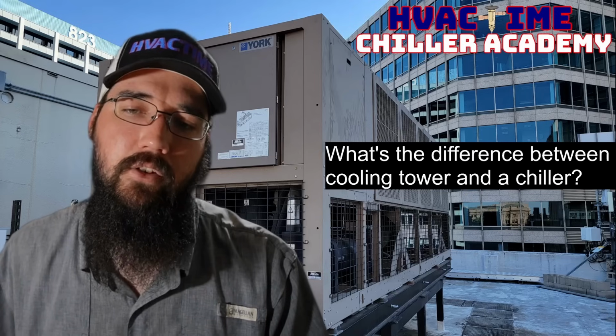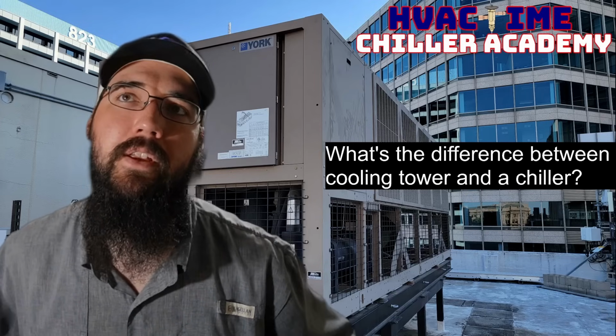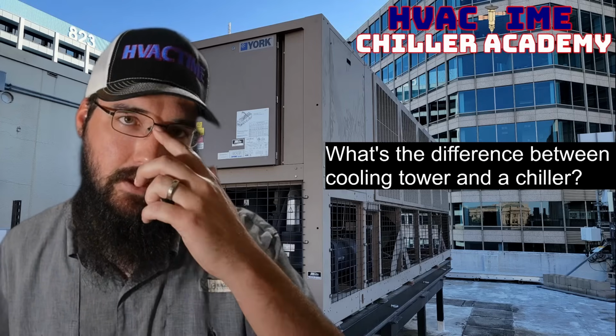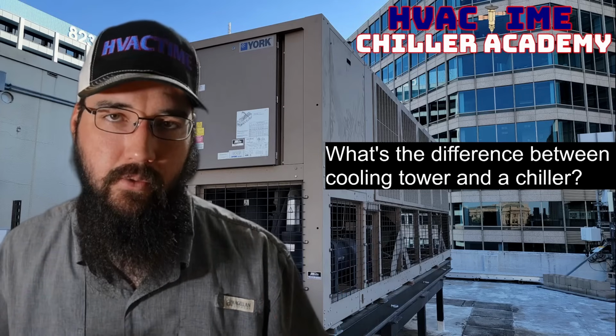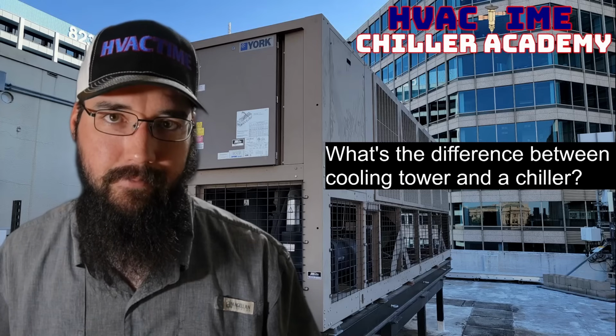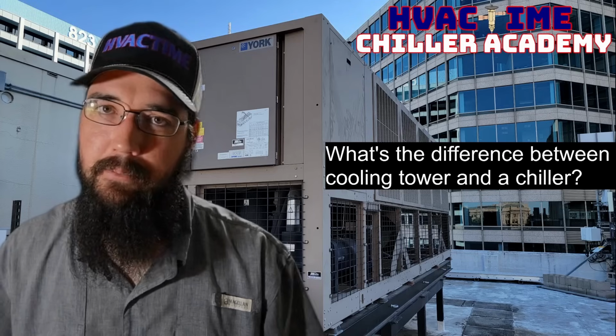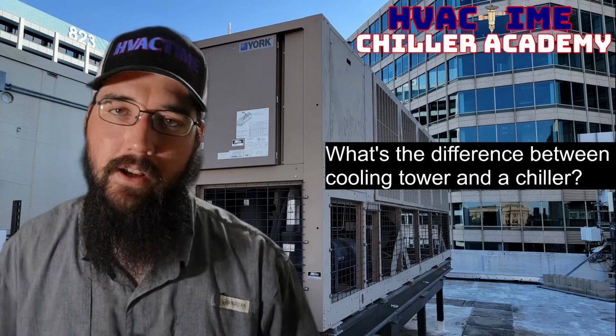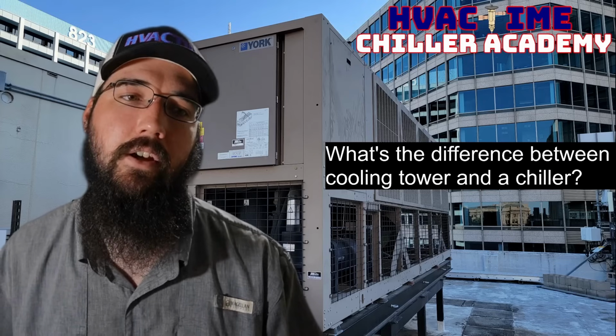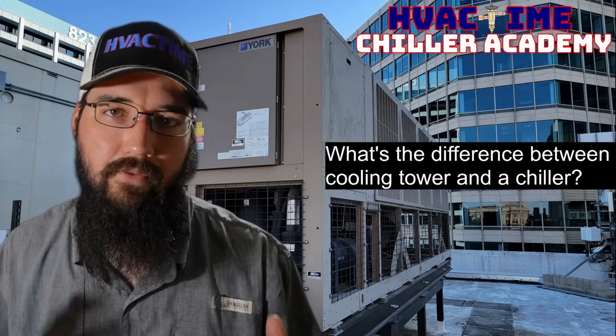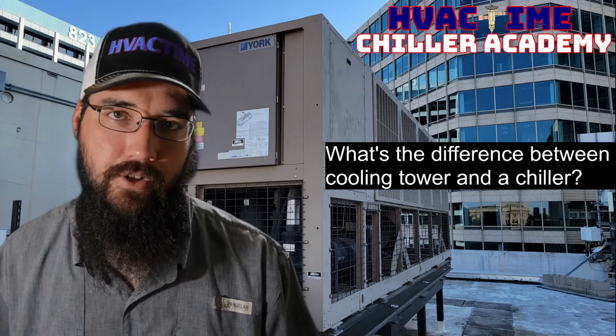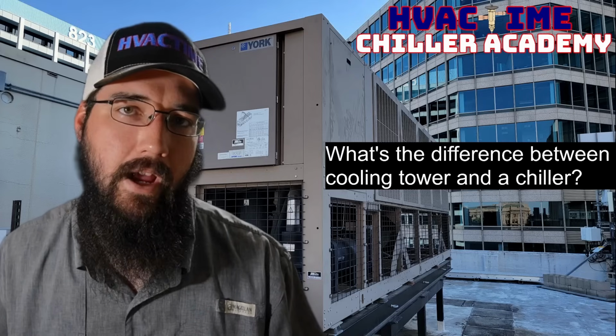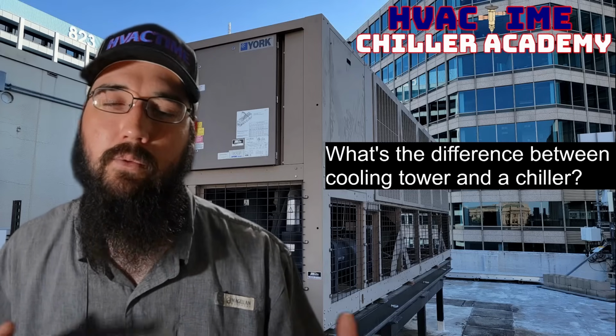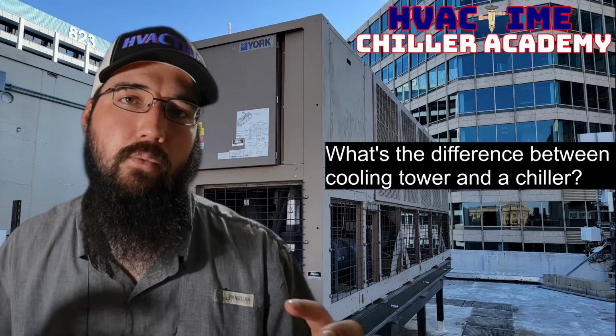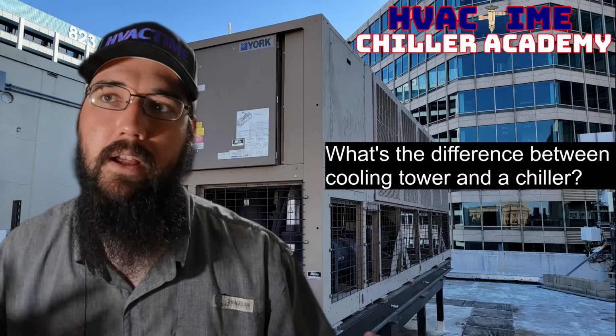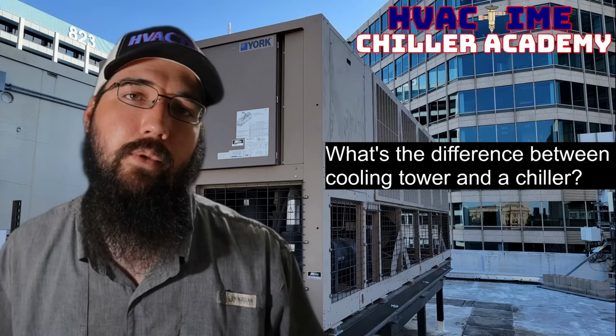What's the difference between a cooling tower and a chiller? So how I define a chiller is a piece of refrigeration equipment that has a hydronic evaporator. That is a form of chiller. It doesn't matter the type of compressor, it doesn't matter the type of condenser. None of those things have any effect on whether it's a chiller or not. If our evaporator has a hydronic function, meaning it's using water or a brine water or glycol water mixture of some kind, regardless of what's flowing through the evaporator, we are cooling a fluid, a water of some kind, hydronic based, then we have a form of a chiller.